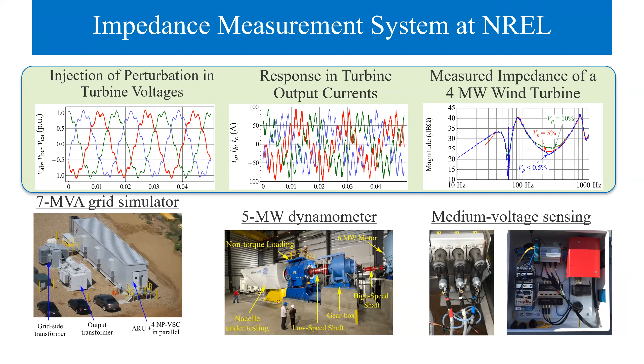NREL is doing a lot of power hardware in the loop testing research to validate these tools. We have multi-megawatt medium voltage grid simulators, full utility-scale wind turbines on a dynamometer, as you can see in this graph, and also high-fidelity instrumentation. Combining all of this allows us to emulate the conditions that a wind turbine will see somewhere in the middle of an offshore wind power plant, and to validate the controls and models that allow us to identify this type of issue.